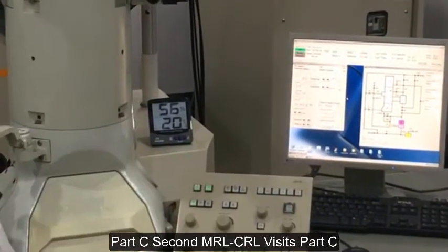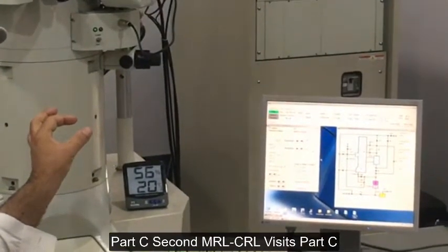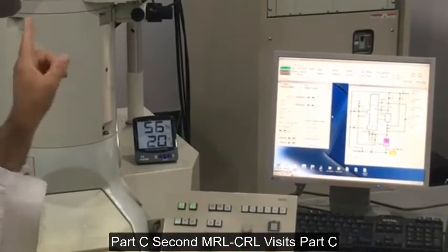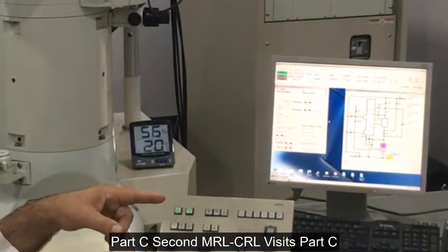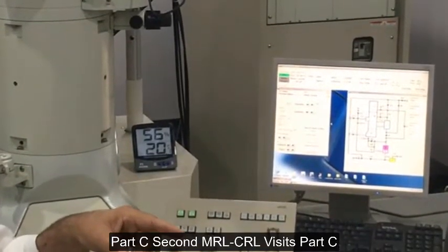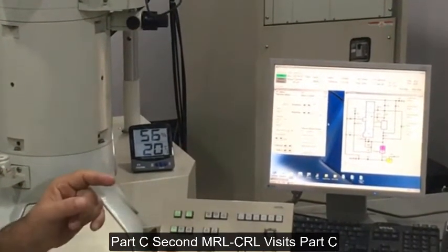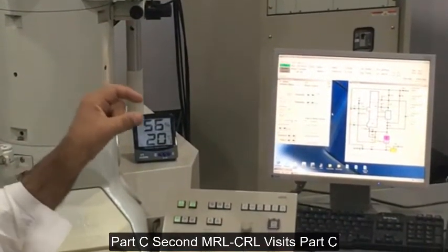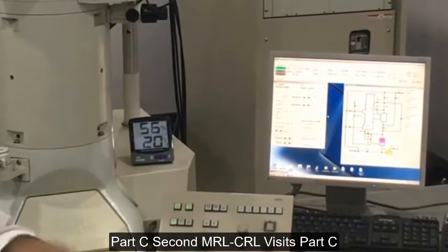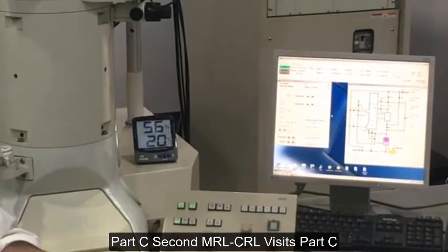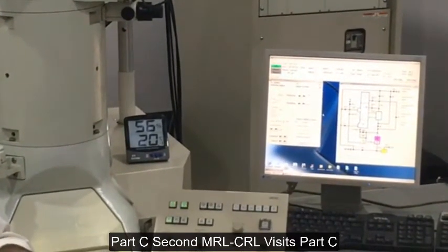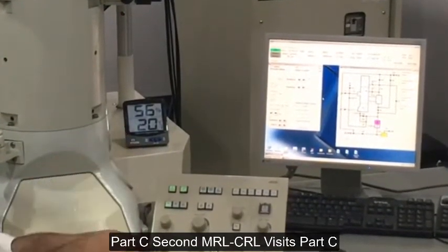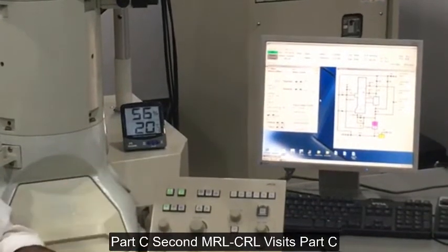In the diffraction calibration, you put a known sample there and measure the D spacings. You know the D spacing. When you know the D spacing, then lambda L is equal to 2D sine theta. No, lambda L is equal to RD. R is the reciprocal lattice spacing, and D is the interplanar spacing. The sample is known, so D is known. R you measure from the diffraction pattern. You measure both, and lambda L is equal to RD.